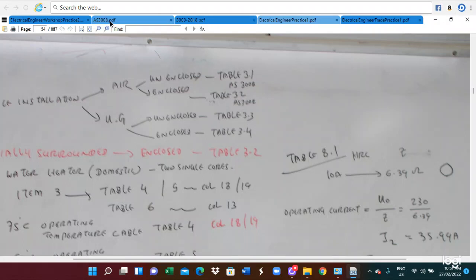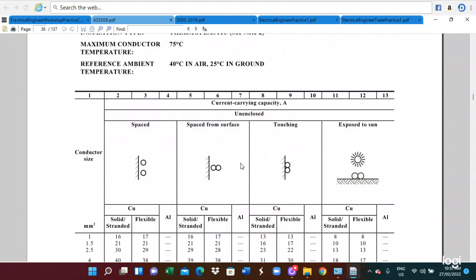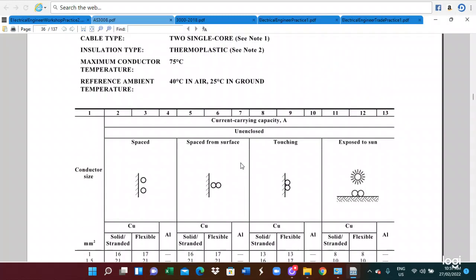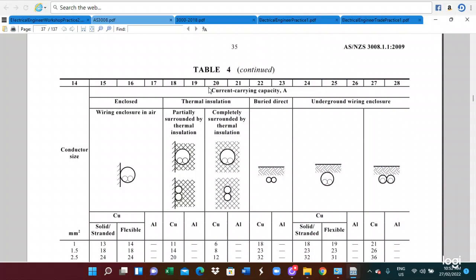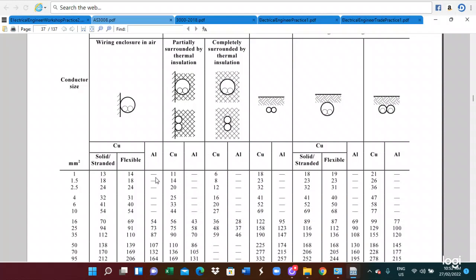Table 4 must be utilized. From Table 3.2, we are referred to Table 4 columns 18 and 19. Column 18 is for copper conductors and column 19 is for aluminium conductors. Looking at Table 4, column 18 for copper conductors.